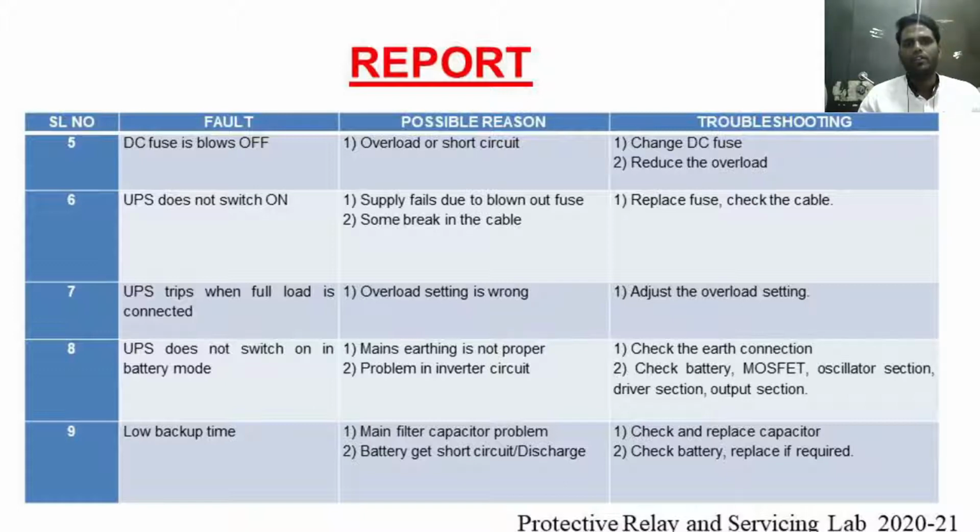So next is that the UPS does not switch on. This may happen because the supply fails due to a blown fuse or some break in the cable. For this, the troubleshooting solution is to replace the fuse and check the cable.